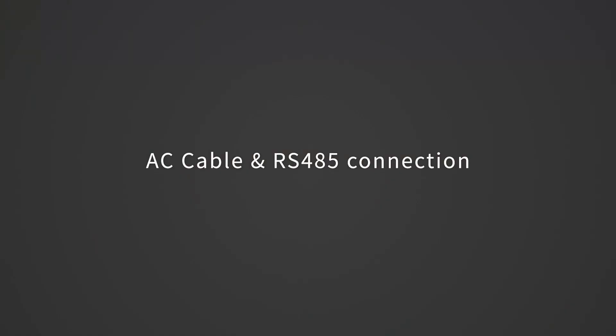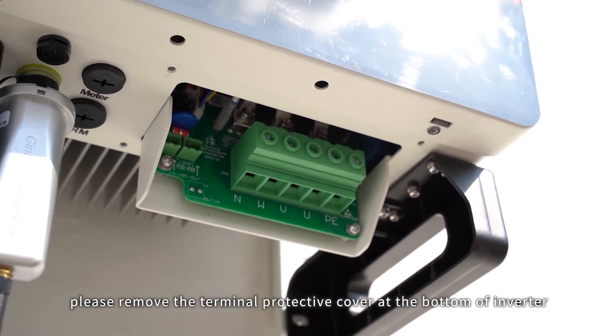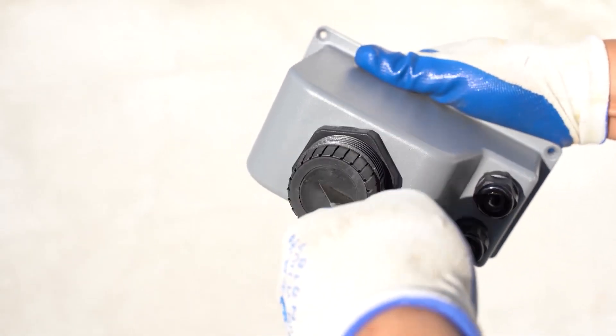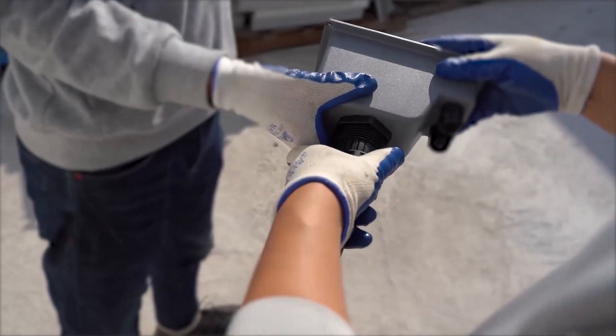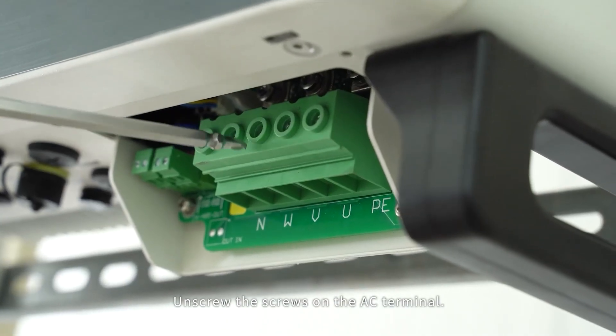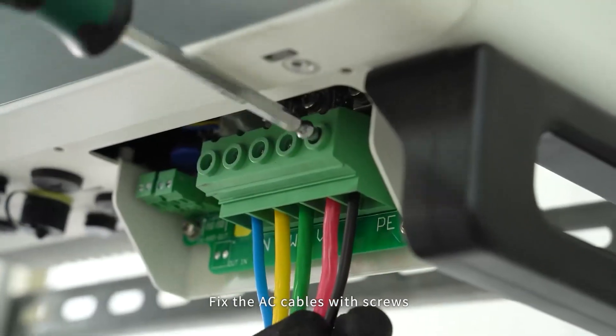AC cable and RS-485 connection. Before connecting the AC cable, please remove the terminal protective cover at the bottom of the inverter. Take out the AC terminal cover in the accessories. Rotate and unscrew the sealing cap. Insert the AC cables through the AC terminal cover. Unscrew the screws on the AC terminal. Align the AC cables with the AC terminals and fix them with screws.